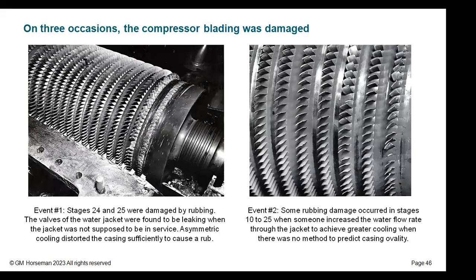This is another occasion. Again, these are about 1946, 47. And this is a case where, again, you can see a few blades have been broken off. This is where somebody increased the flow through the cooling jacket to see what would improve. Well, as I mentioned, as you cooled the compressor casing, it shrank and reduced the running clearances. They had no method of calculating transient distortion effects in those days. So unfortunately, the person who did it cooled it so much that, again, it took some of the blades off.